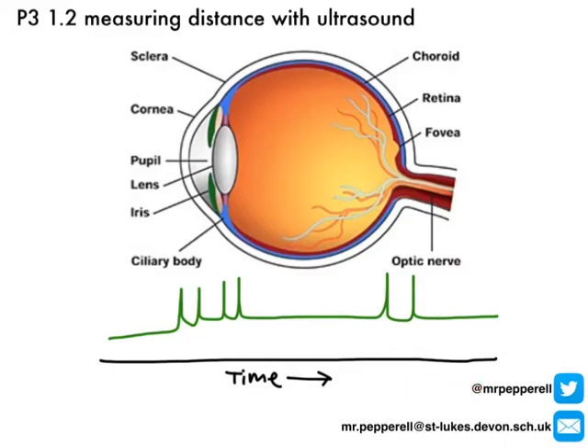I've sketched out a rough A-scan here with my peaks and the time going along the bottom. This shows that if we know what interfaces my pulse has travelled through on its journey through the eye, I can match up the transit times with those different interfaces. You can see I've got a peak corresponding to the front of the eye, a peak for the back of the cornea, peaks for the front and back of the lens, and a transit time for the back of the eye — so I can use that to work out where my lens needs to focus.